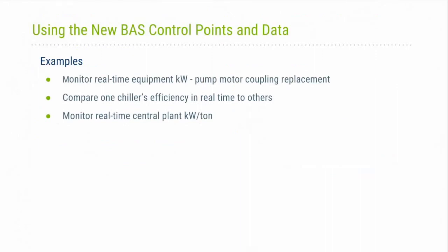So here's a few examples of how the additional BAS points and functionality is useful. First, pump KW is part of the dashboard on the BAS workstation. Each pump's KW is visible on the same screen. We actually had a situation where O&M noticed that one of the pump motors wasn't pulling the same KW as the other pumps. O&M staff determined fairly quickly that the pump had a blown coupling and replaced it.